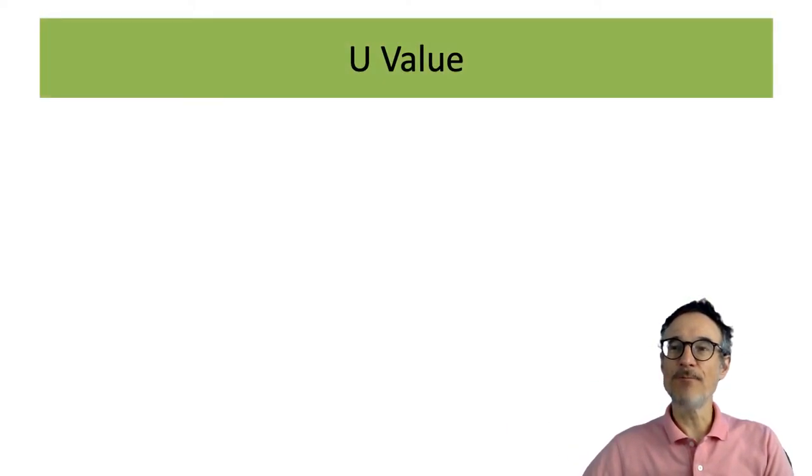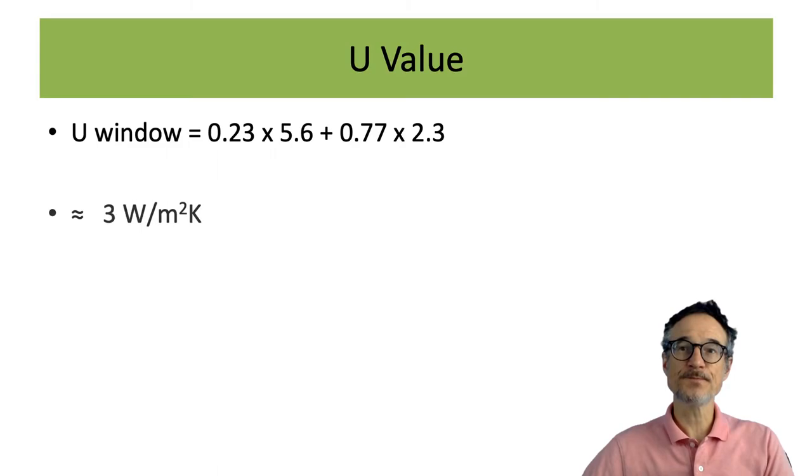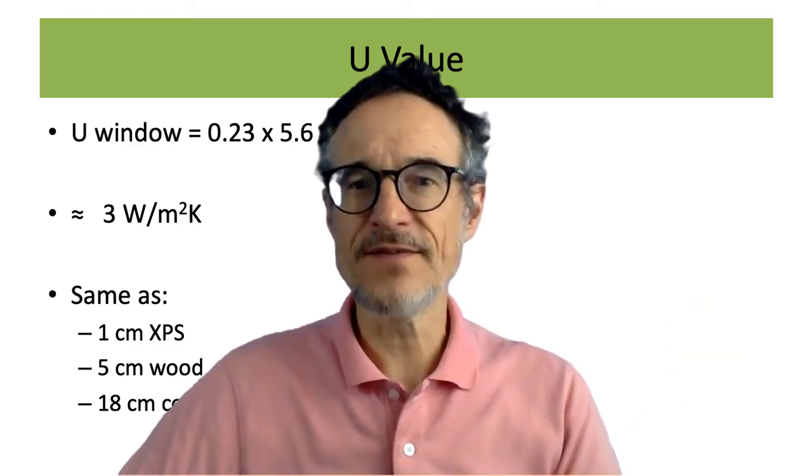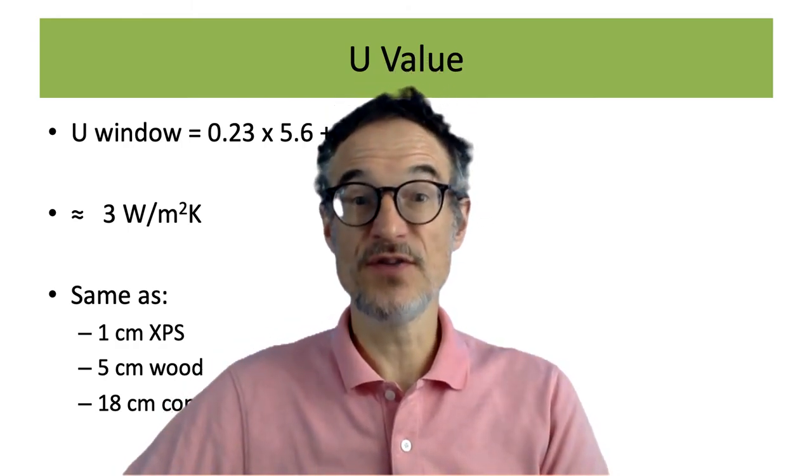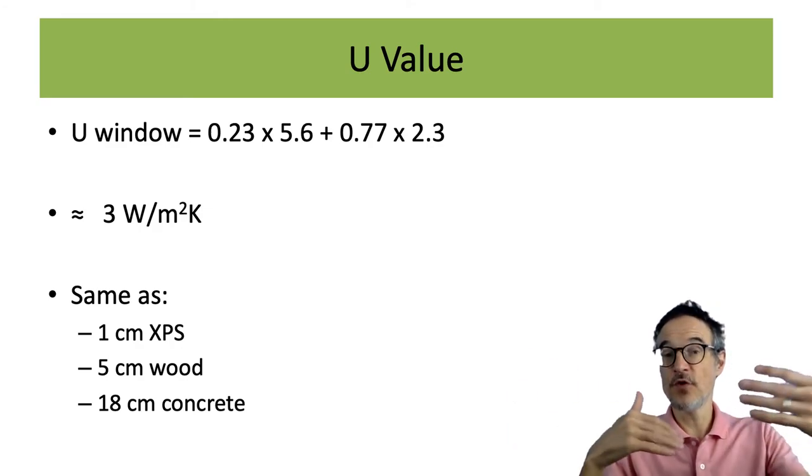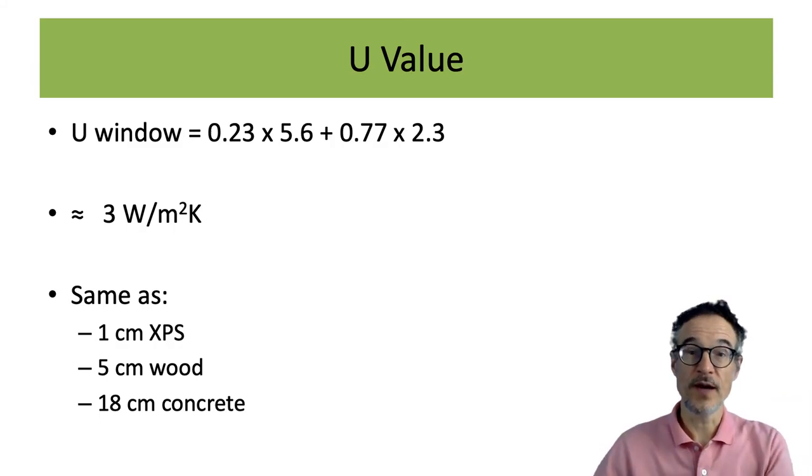And so we can put these all together, and we get around so that the glass is doing better than the frame, and it comes to something like three watts per square meter Kelvin. I don't think we can really give a more accurate answer than three. It's around three. This would be the same as one centimeter of XPS, same as five centimeters of wood, the same as 18 centimeters of concrete, just to compare the performance of the glass with what you might have in the walls.